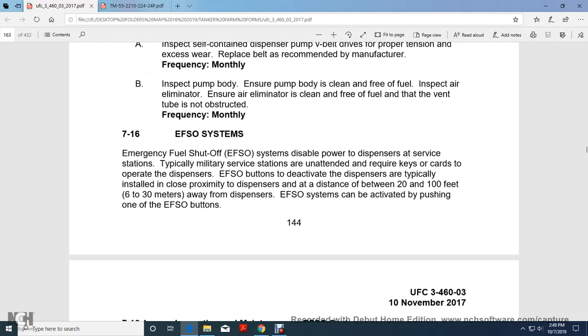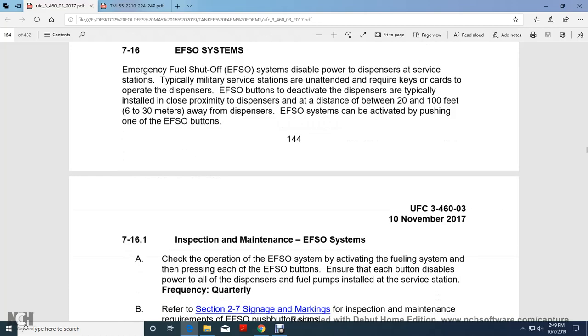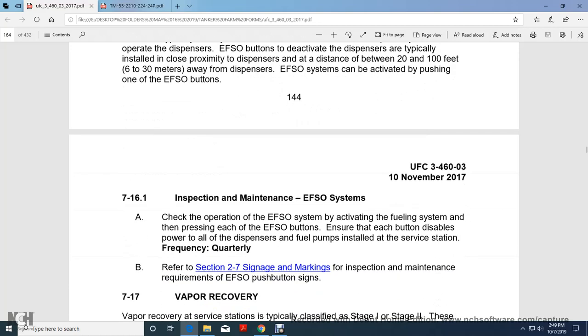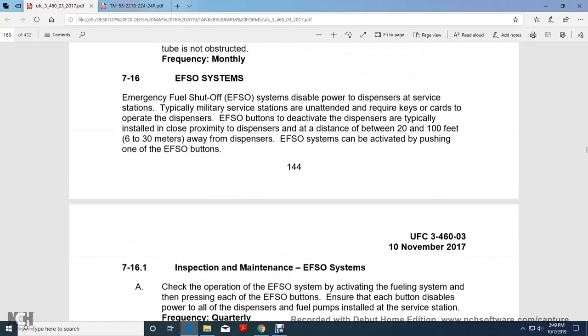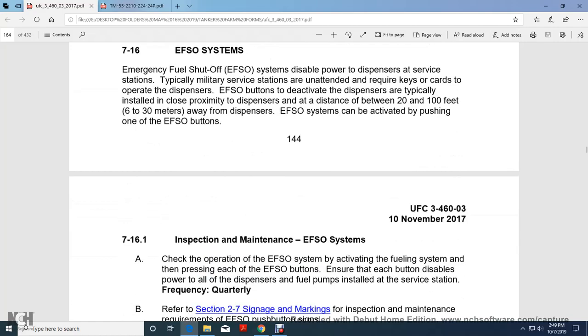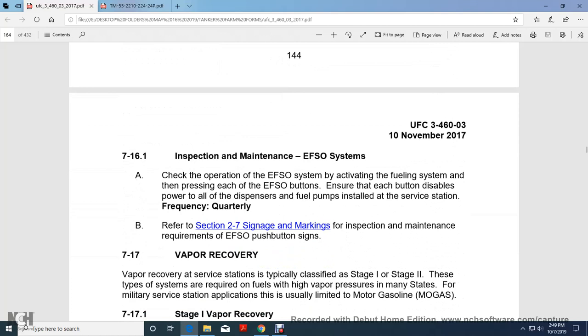Emergency fuel shutoff system. The emergency fuel shutoff system disables the power to dispense for the service of the station, or for the typical military service of the station unattended, with the required keys and cards that operate the dispenser. Emergency fuel shutoff buttons deactivate the dispenser. They are typically installed in close proximity to the dispenser, 20 to 100 feet away. Emergency fuel shutoff systems can be activated by pushing one of the emergency fuel shutoff buttons. Inspection maintenance.